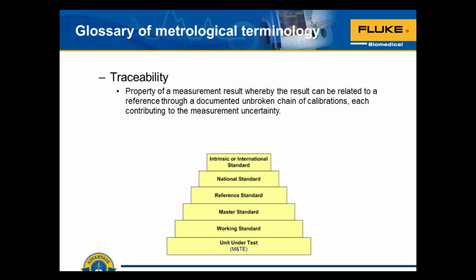So in this case, the DC volt is a primary unit of measure, and it is created in a lab, and it is traceable through transfer standards right down to the DMM that we use, or the electrosurgery analyzer or electrical safety analyzer that we use as examples, and to the medical device itself where DC volts matter and where you're going to be making measurements for performance specifications. So traceability is important for you to understand and have enough information so that on audit you can show that you know and are in control of the calibration of your test tools and the medical devices that you're responsible for.